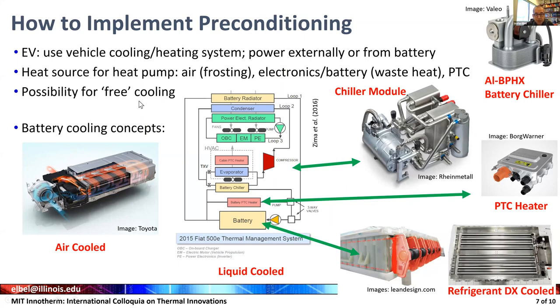One important aspect to consider is whether free cooling is available—that is, situations where the ambient temperature is low enough that you can readily reject heat to it. It's good to harness that temperature difference without running the vapor compression system. This is what we call free cooling: you just dump the battery heat to the ambient without driving the vapor compressor.